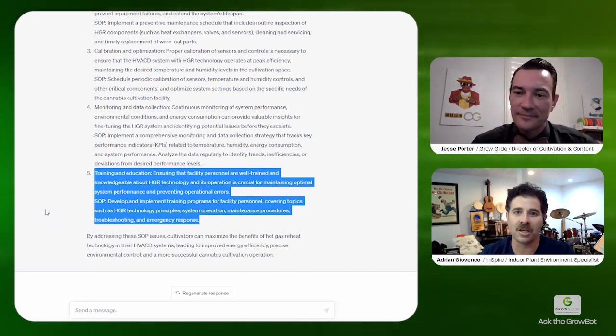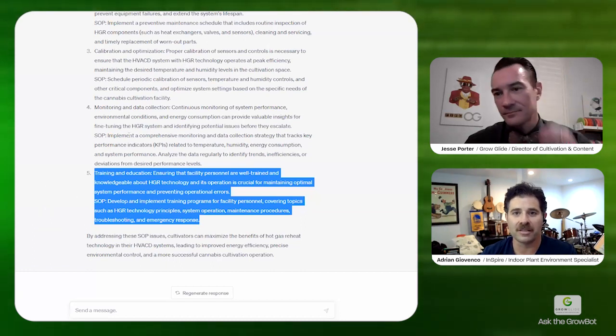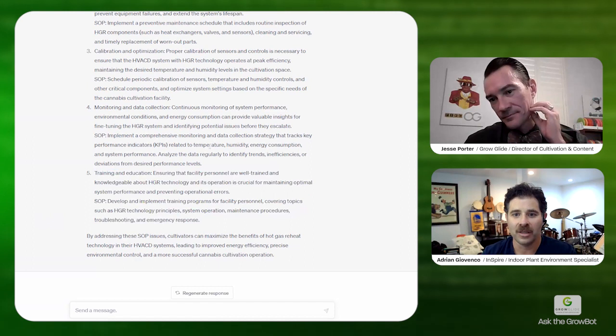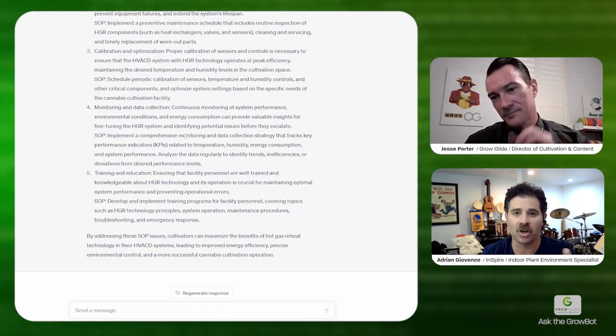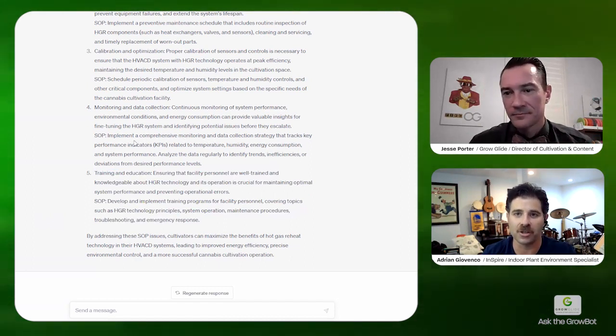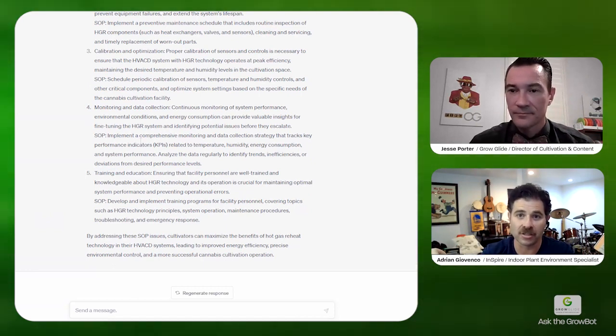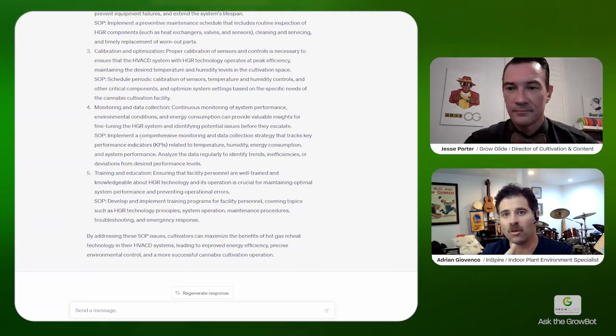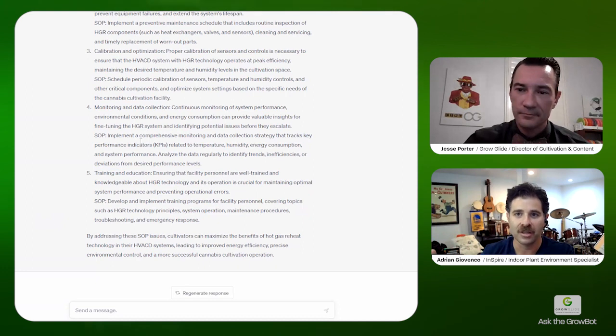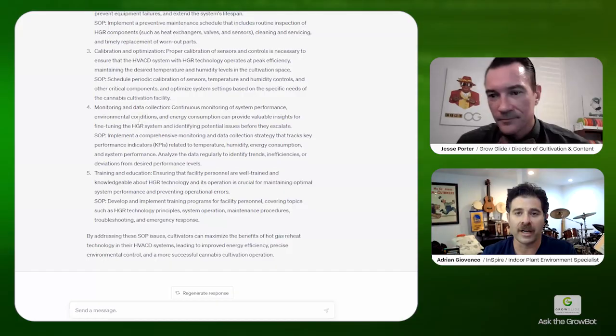The closest we've found to date, until we get better sensing devices inside the plant canopy, is systematically determining what that leaf temperature to air temperature offset is, and then setting that in the control system that's controlling the HVAC dehumidification system. So when you're looking at the data and seeing VPD overlaid on your trend graphs, that's real leaf VPD, not air VPD.